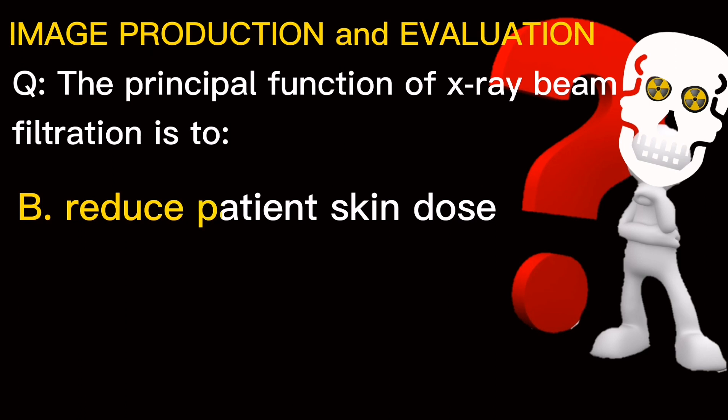Reduce patient skin dose. It is our ethical responsibility to minimize radiation dose to our patients. X-rays produced at the target comprise a heterogeneous primary beam. There are many soft or low energy photons that, if not removed, would contribute to greater patient dose. They are too weak to penetrate the patient and expose the image receptor — they just penetrate a small thickness of tissue and are absorbed.